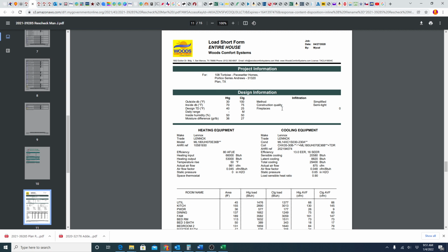So that's kind of why you look for these, other than the fact that it also can carry up to a $2,000 fine for everyone that's missed for your municipality. And you'll look for semi-tight construction generally, anything that's modern construction. The semi-tight designation will be between 3 and 5 ACH, which are air changes per hour.